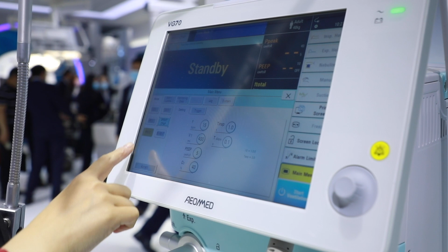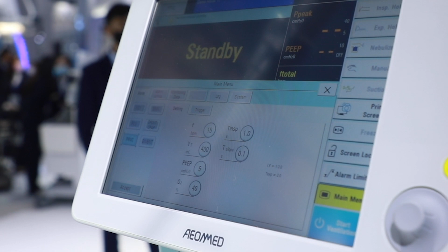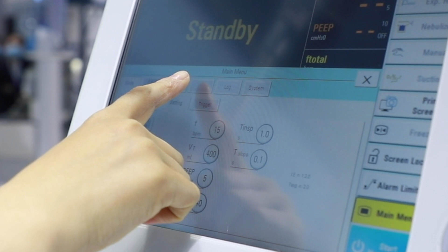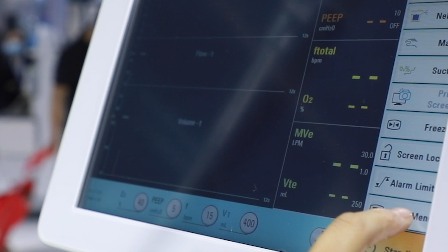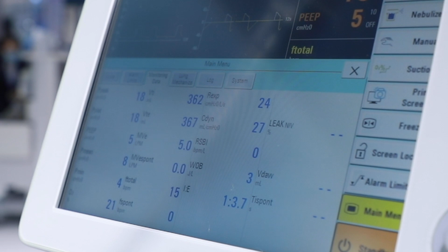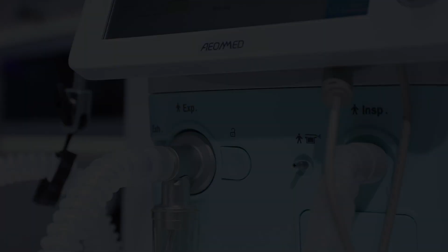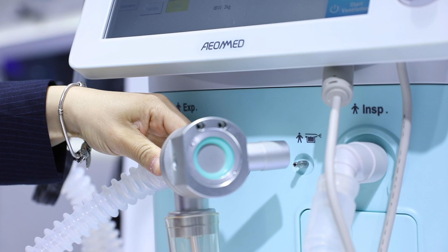Smart ventilation mode, pressure regulated volume control, auto-adjusts the pressure support level to achieve the target tidal volume, enhancing lung protective strategies. It also applies intelligent leak compensation technology, which allows it to achieve a 60 liter per minute capacity, with auto-detect and adjust leak compensation. Comprehensive lung mechanics monitoring includes compliance, airway resistance, intrinsic PEEP, and time constant. Rapid shallow breathing index and work of breathing provide accurate reference for weaning. Last but not least, cost-effective solutions. The unique metal-based autoclavable heated exhalation valve with built-in flow sensor gives optimized performance with the lowest user cost. That's a very brief introduction to our VG70.